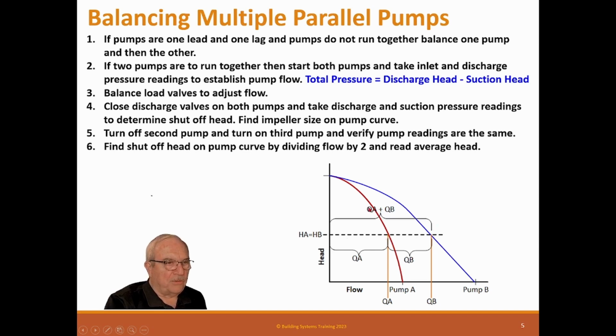Now, where do you get this curve? It should be in the submittal. If you're running 2 parallel pumps, I have to warn you, it probably won't be there, because the pump supplier doesn't really know whether they're running parallel pumps or not either. So what happens is you request it and the vendor can create that curve. It's on their computer. They just push a button and they can create a 2-pump curve. And that's what you need to really evaluate the system and to know where it's running on full GPM.